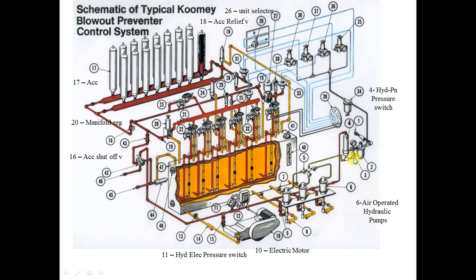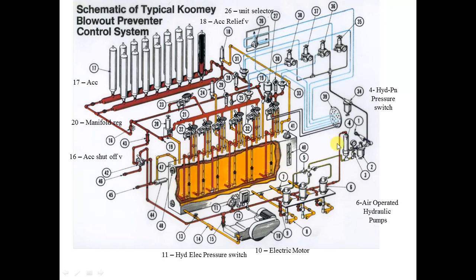The bypass valve is only opened when you need to get high pressures from the air pumps, and at that time you must reset number four again. Number four is called the automatic hydro-pneumatic pressure switch — 'hydro' meaning hydraulic oil from the tank or reservoir, and 'pneumatic' referring to air.